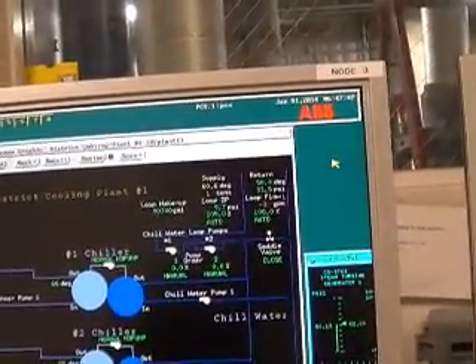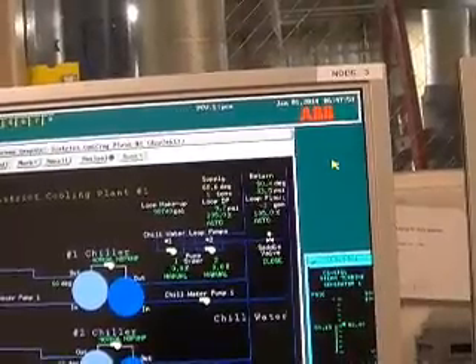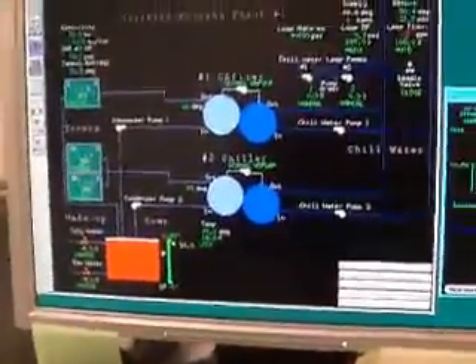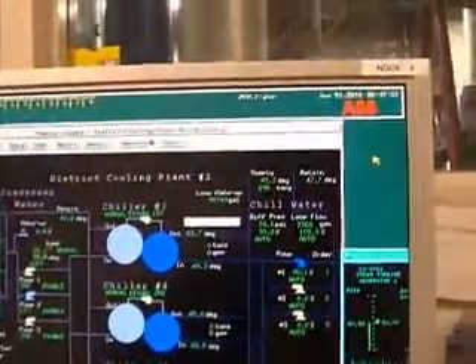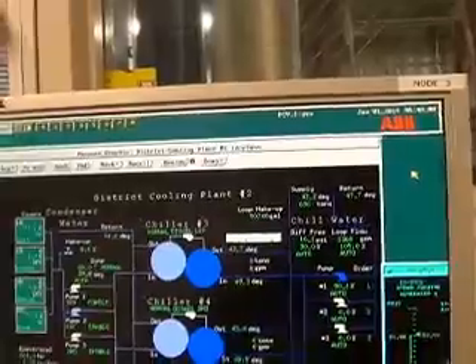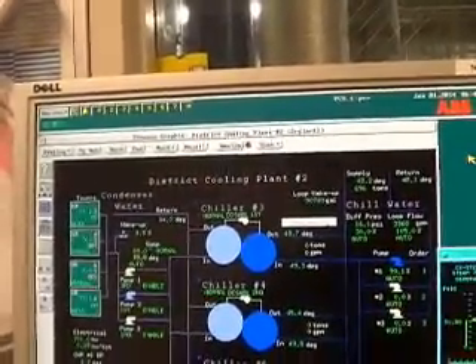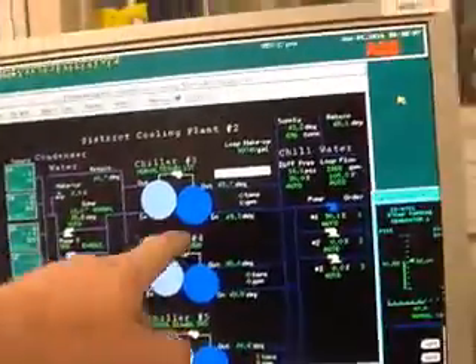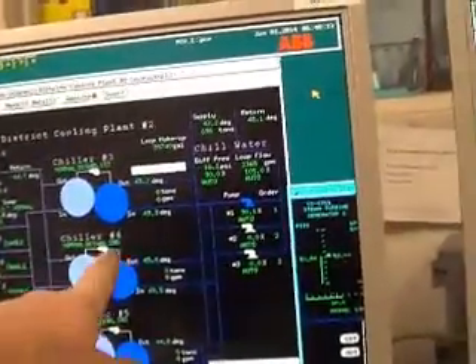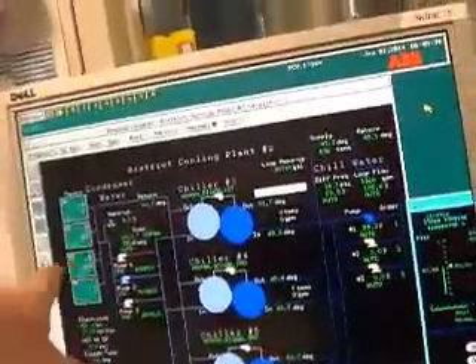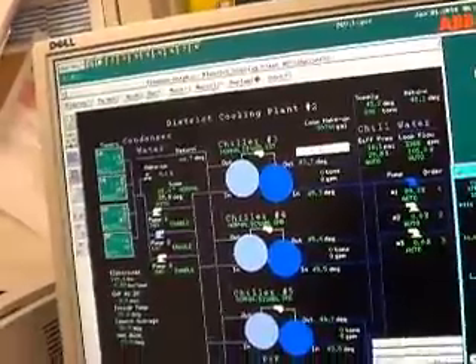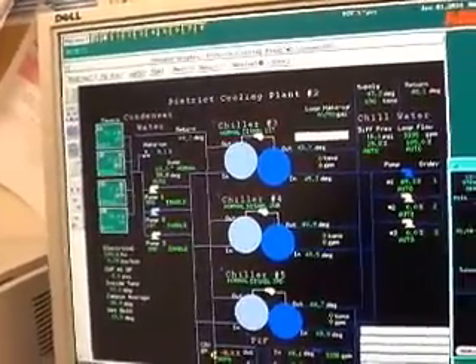I can toggle over to check chill plant 1, which is off, and I see the pumps are off. Everything's off. Oh, okay, red is a bad thing. It just means the sump is overfilled. That happens. And here's chill plant 2. The cooling towers are at 77%. I got 2 towers on here and here. I'm putting out 43-degree water, 48 return, 1 condenser pump, and flat plate is down here. It's transferring that heat over to the towers, and it's evaporating water as it flashes off, just like a swamp cooler. Does that year round. You've seen the ice.